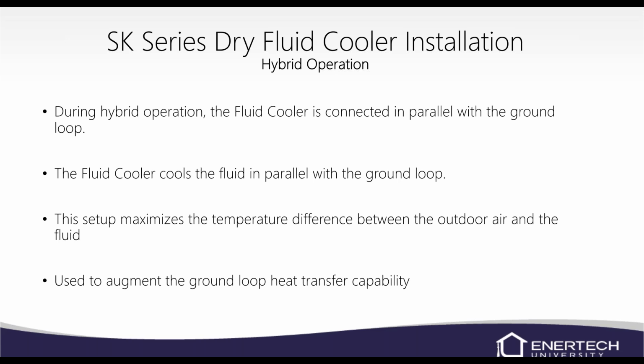In hybrid operation, the fluid cooler is connected in parallel with the ground loop. Basically, the fluid cooler cools the fluid in parallel with the ground loop, so it's working in conjunction with the ground loop. This setup maximizes the temperature difference between the outdoor air and the fluid itself. Normally, it's used to augment the ground loop. So if you've got a hot loop in the summer, you can add this to it rather than add more loop to the ground, to the source water.